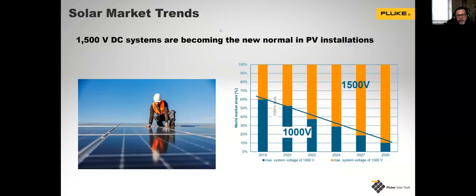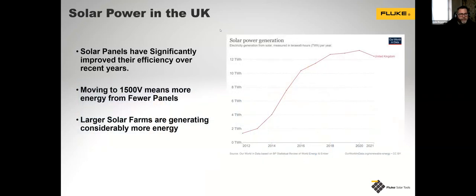The market trend is increasingly going to 1,500 volts as opposed to traditional 1,000 volt systems. One thing we should note is that these 1,000 volt systems aren't going to disappear. It's just a percentage of the actual market. So the market's going to increase. Traditional 1,000 volts are still going to be there. They are installed with a view to being there for a long time, but because of things like the increase in solar farms and commercial properties going up to the 1,500 volt systems, you will see that percentage going down. But there will still be a need to measure 1,000 volt systems.